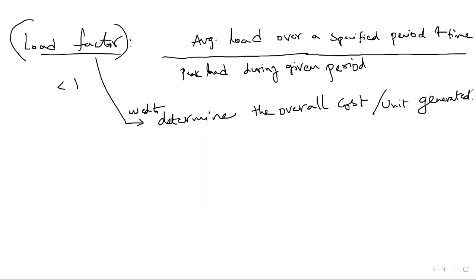If you want to consider it for annual purposes, then the annual load factor formula becomes the total annual energy, that is, the average energy consumed, divided by the annual peak load multiplied by the number of hours in the given period, in the sense 365 into 24, that is 8760 hours, which we need to consider if we want to calculate the annual load factor. Okay, done.